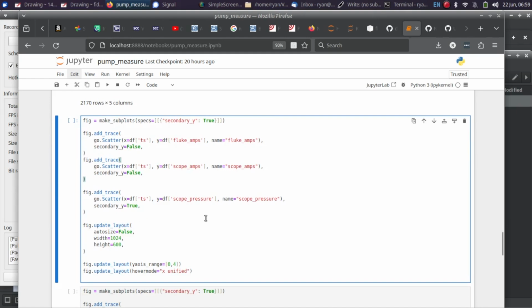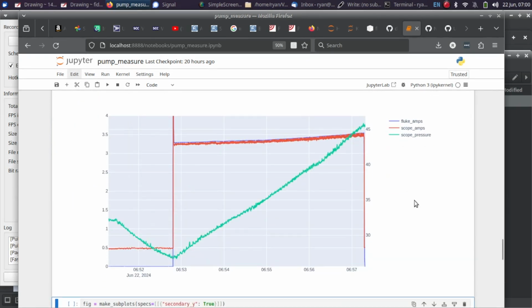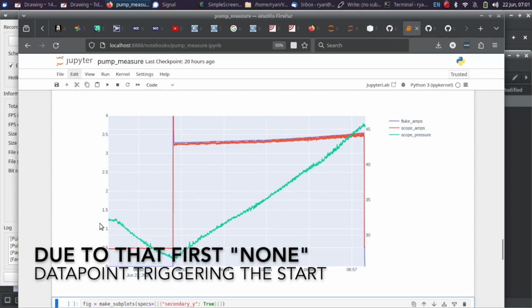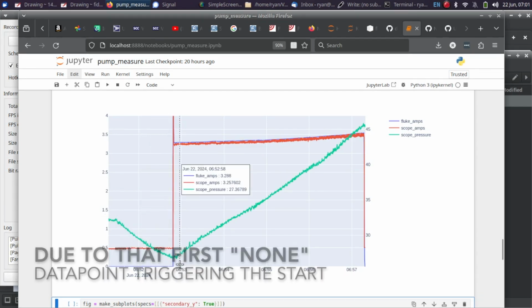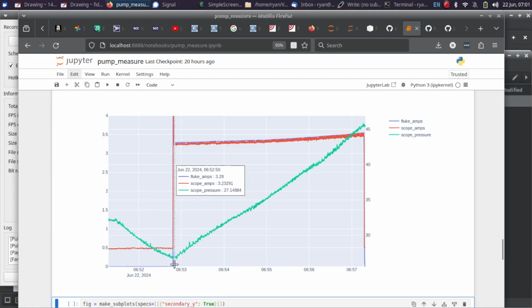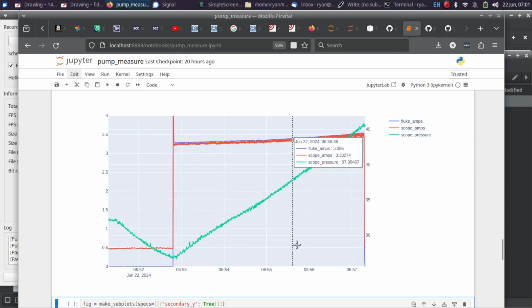So I'm using Plotly to make a visualization of some of the data here. In this particular example, it was capturing the pressure and everything as it was decreasing, so you can see the pressure drop and exactly where the cut-in was. The green line is the pressure. There's the open valve period here. Then we can see both current readings show when the pump started, a couple second delay to when I close the valve, and then building pressure.